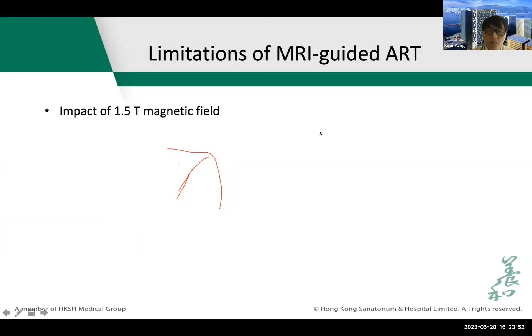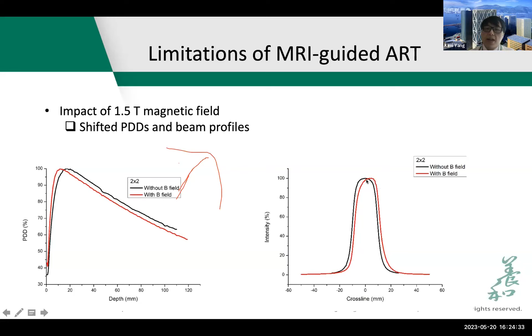The first impact is the shifted PDDs and beam profiles. As you can see here, the red curve indicates the PDDs or the beam profiles measured with the magnetic field, and the black one is without the magnetic field. For the PDD, it will be shifted towards the surface. And for the profiles, it will be shifted in the plus X direction. Of course, it depends on the direction of the magnetic field. So the profile will no longer be centered compared to the conventional linac.